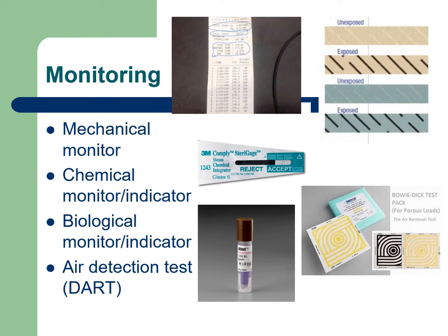The black card that you see means that it was a good test, that all the air was removed. The yellow is before the test. If we were to see a combo of the two, maybe black around the edges and yellow in the middle, that would tell us that something's not going right with the steam sterilizer and we need to have it looked at before we cook anything else in it.